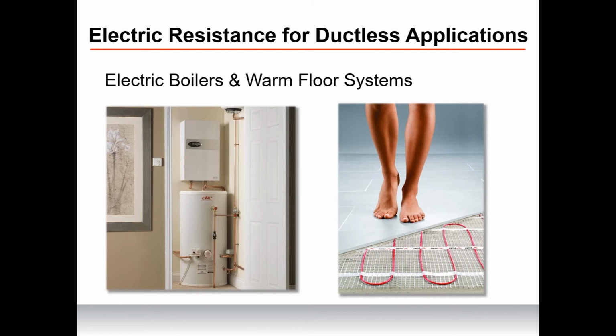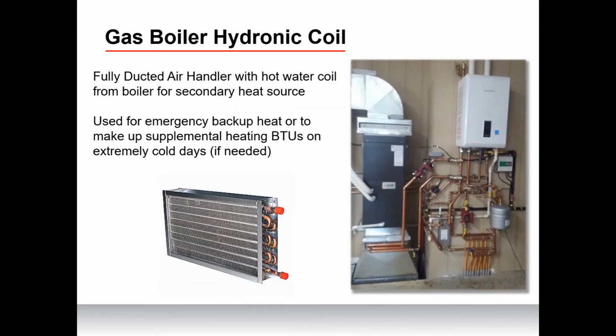Lastly, electric warm floor systems are very popular for backup heat in smaller spaces like bathrooms or kitchens. So let's say we're looking at a home design and we don't have direct space conditioning going into the bathroom, which is very common, especially if it's an interior space. Putting a little bit of electric warm board or electric in-floor underneath the flooring for that bathroom or for the kitchen really helps from a comfort standpoint. It's not really a backup emergency type system because it's not throughout the entire house, but it's really great for comfort in bathrooms or kitchen areas. A lot of times where you have tile flooring.